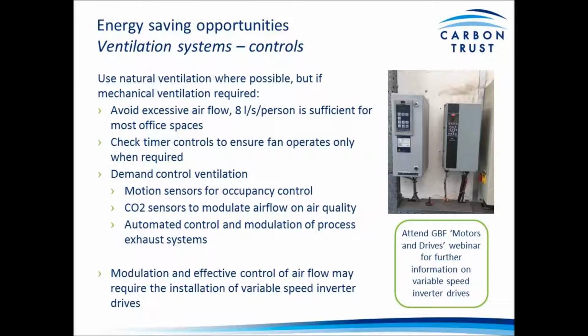But multiply the number of people you have by that figure, and then compare that to the fan specification in your O&Ms, or the operation and maintenance manuals, or with your maintenance team. There may be scope to reduce the airflow rate to your building and reduce the energy consumption of your fan systems. Review time settings. Again, this is something we've mentioned with heating. Quite often we see ventilation systems running out of hours, running for longer periods than necessary, so check that you have effective time control.